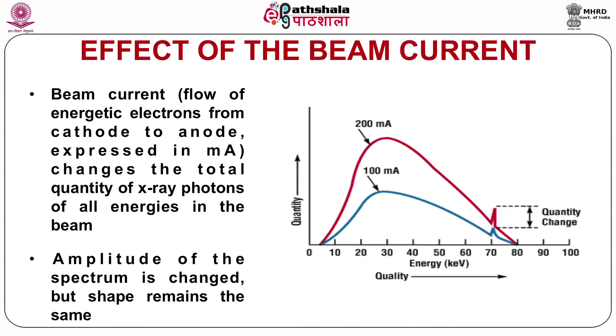The figure shows the spectrum of an X-ray tube operated at 80 kVp. In the first case, the tube current is 100 mA, and in the second case, the tube current is 200 mA. So now we see here that there is no change in the nature of the spectrum except the change in the amplitude of the spectrum. Thus, varying the beam current varies the quantity of X-ray but does not alter the quality of X-ray.